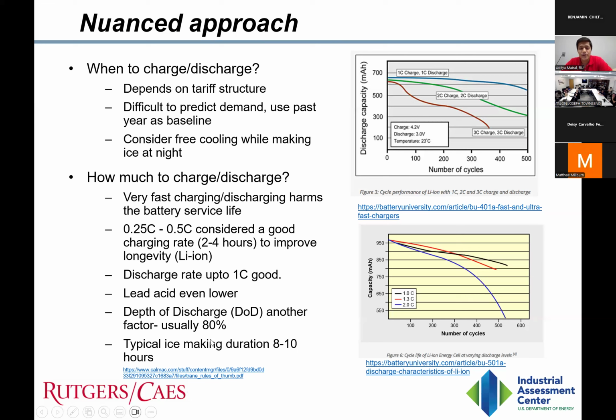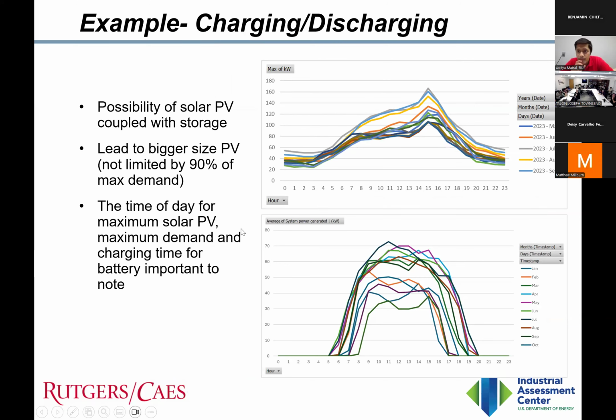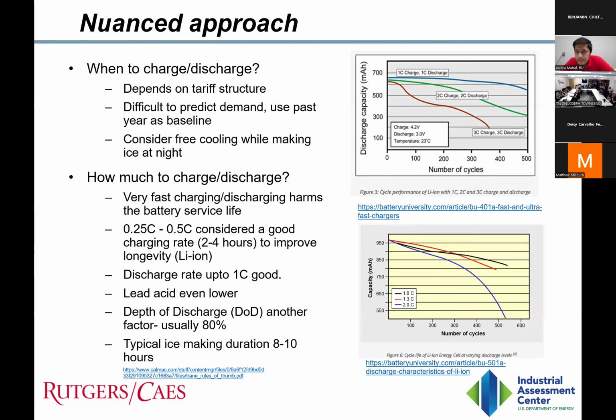And then typical ice making duration — I know I'm speaking a lot on electrochemical batteries, but my goal for today was to spend more time on electrochemical and not a lot on ice storage. I have some links here that will help with the ice storage calculations, from well established big companies. Typical ice making duration is about 8 to 10 hours, so we need to consider those hours. If we have a chiller working 24 hours, we need to consider those 8 to 10 hours to make the ice, and then the next hours to use it. So ice storage is a form of thermal energy storage.